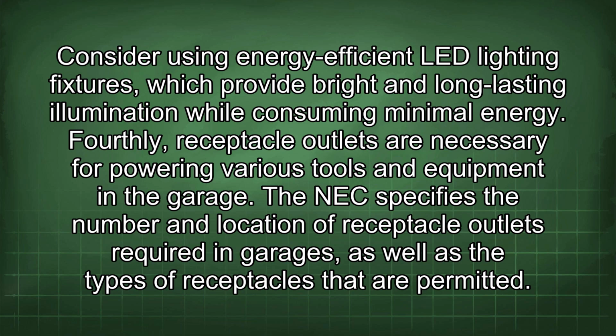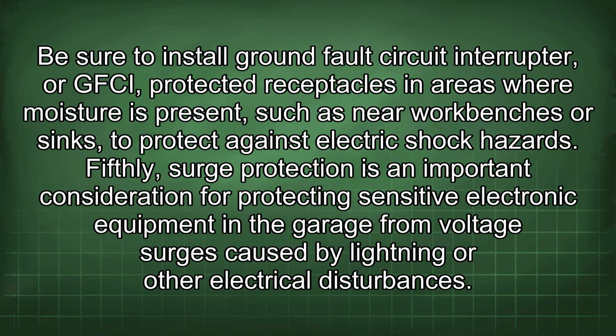Fourthly, receptacle outlets are necessary for powering various tools and equipment in the garage. The NEC specifies the number and location of receptacle outlets required in garages, as well as the types of receptacles that are permitted. Be sure to install ground fault circuit interrupter, or GFCI, protected receptacles in areas where moisture is present, such as near workbenches or sinks, to protect against electric shock hazards.